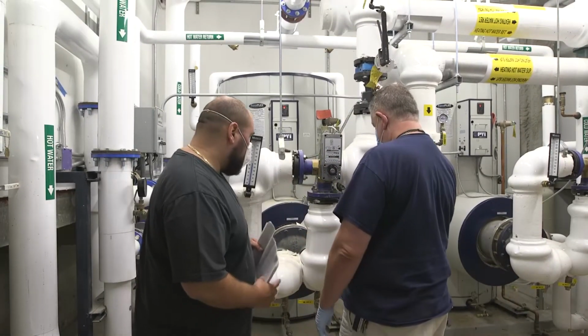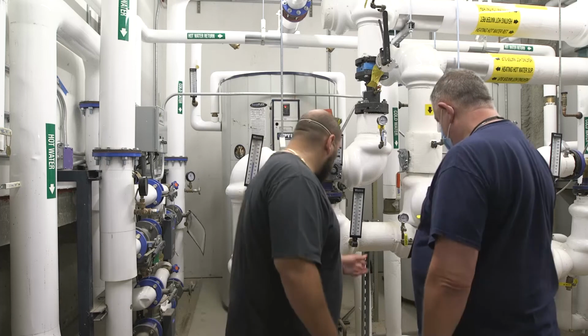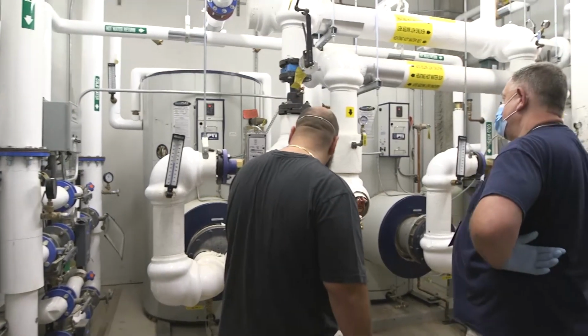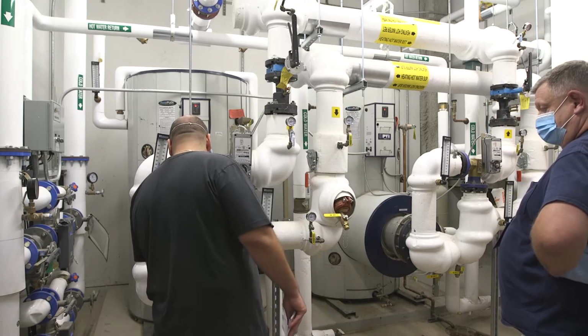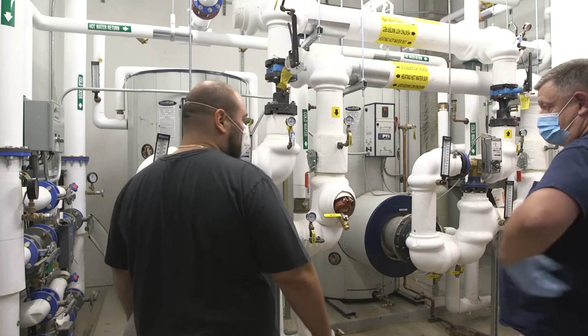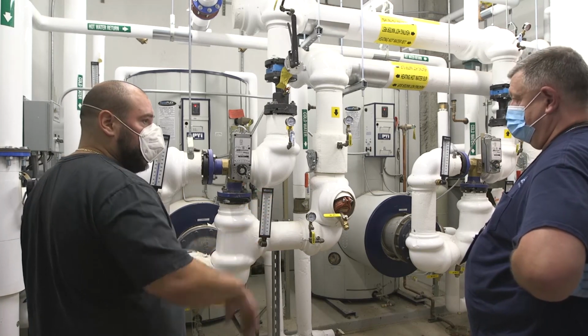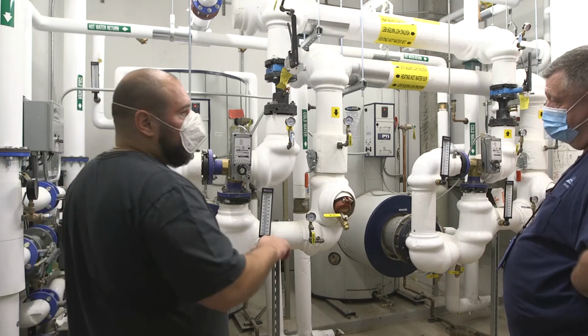There's like 2 different gaskets in there too. Yeah, it would just slide right out. But it's connected to this pipe. So in here there should be a union somewhere. They might have covered it. Maybe not, I don't know. But you definitely need some type of union here to be able to slide it. And there's 2 gaskets in there that you would need to replace. And when you put it back, you need to torque it down to a certain amount of pounds.